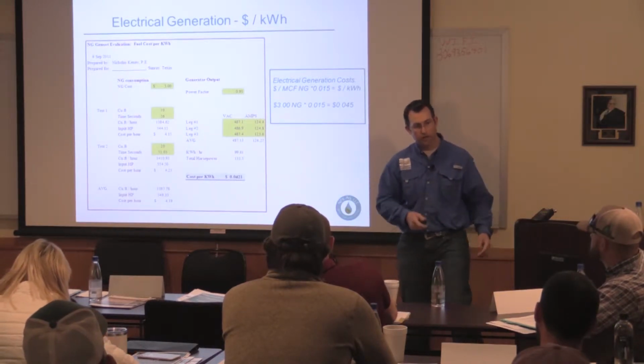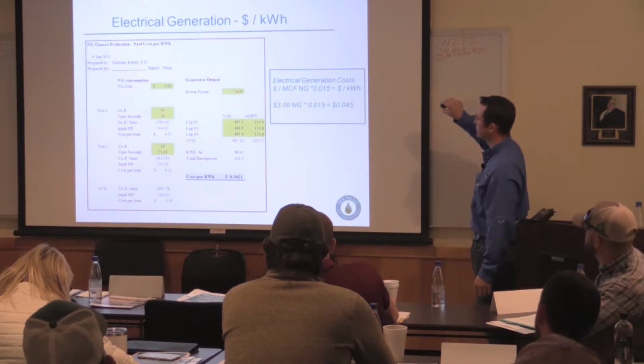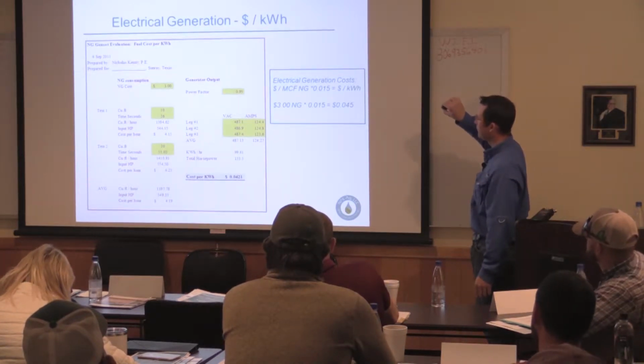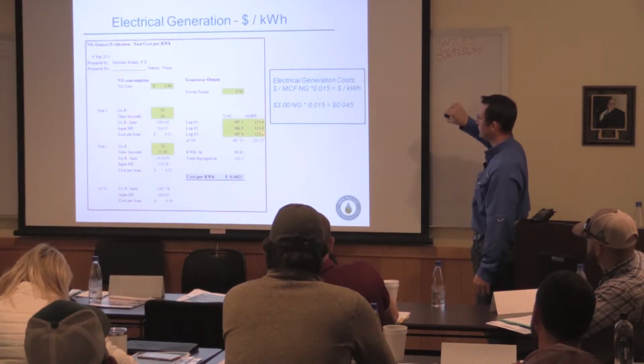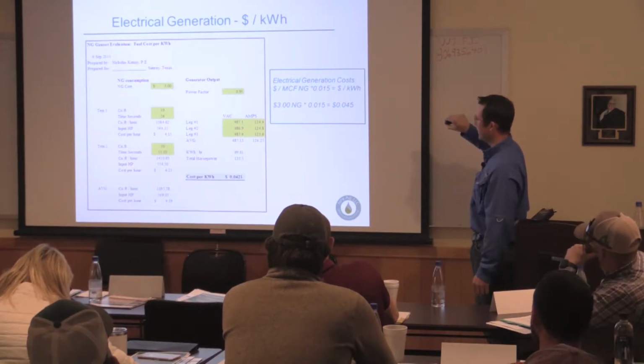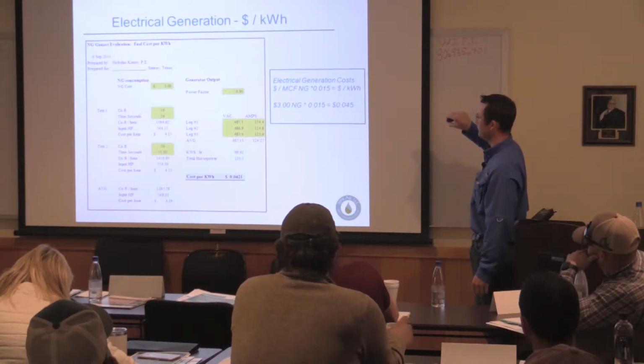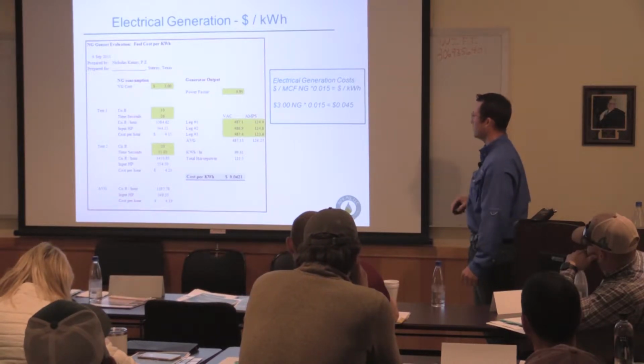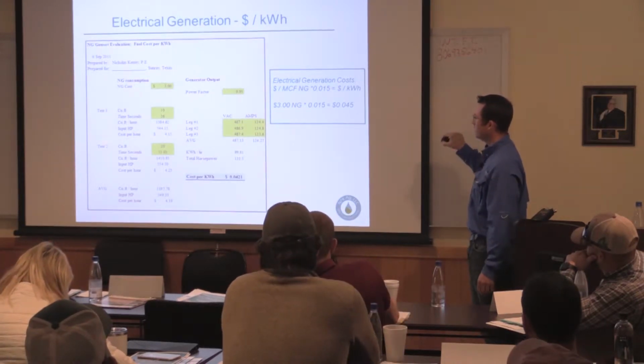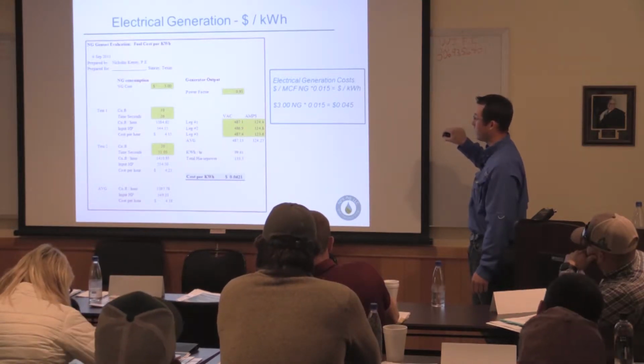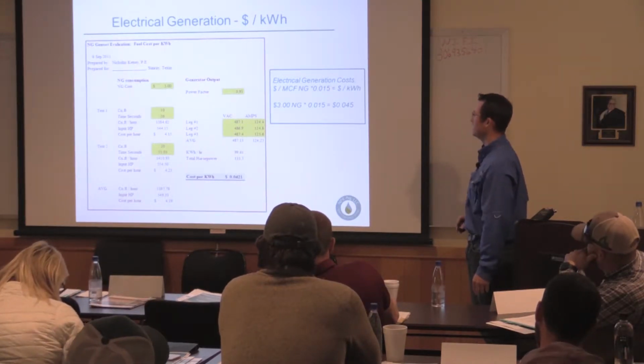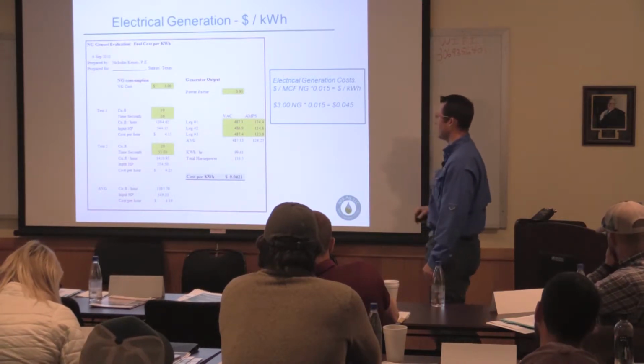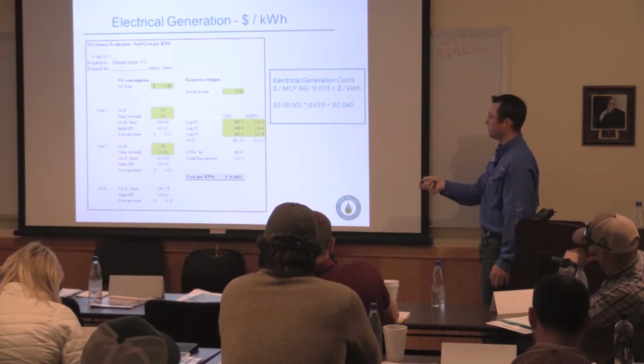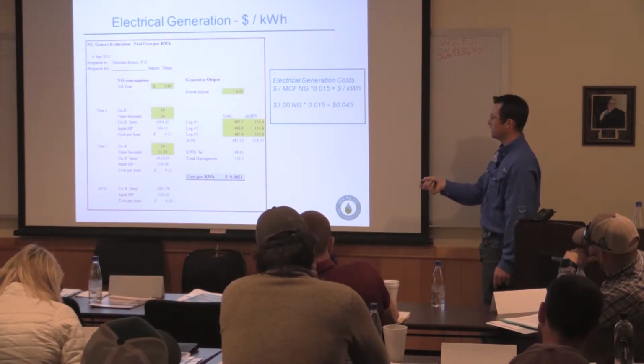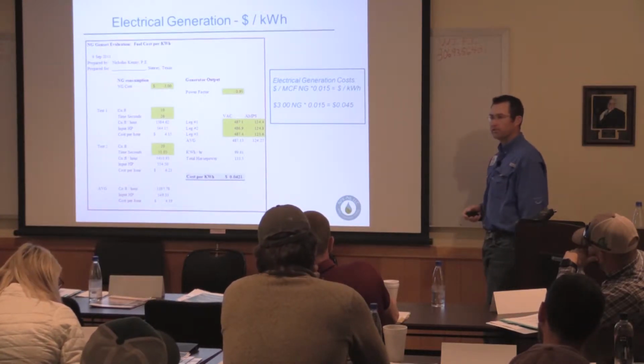Compare that to the output, or generation side. The generator output at a measured power factor of 0.95, generating at just shy of 490 volts and 124 amps. Working through the math, you get kilowatts, same as kilowatt hours per hour, generating just under 100 kilowatts, total horsepower of 133. What we come up with is a cost per kilowatt hour at this rate of 4.2 cents.